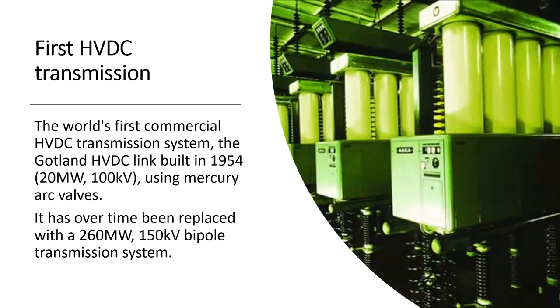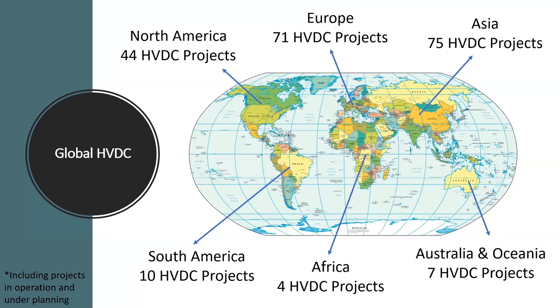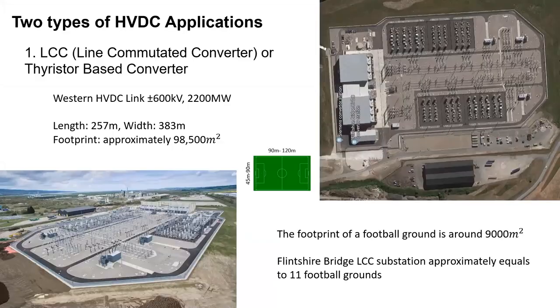The world's first HVDC link that was put in commercial operation was almost 66 years ago. And it had a rating of 20 megawatt at a voltage of 100 kV. Over time, this link has been replaced and upgraded with a higher rating at a higher voltage. Across the globe, there are now 211 HVDC projects and counting. This slide shows where those HVDC projects are. And these projects are either LCC or VSC. I'll talk about LCC and VSC on the next slide.